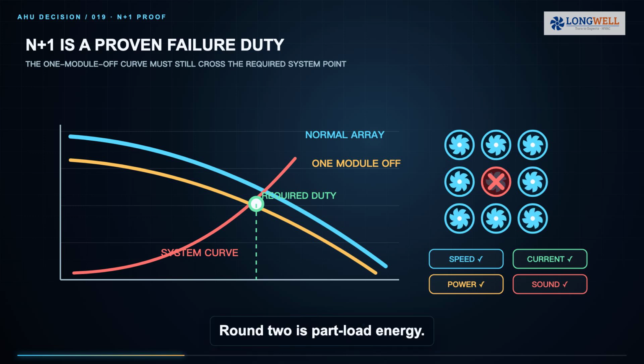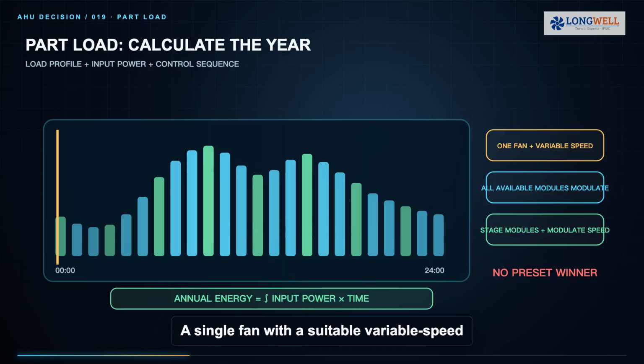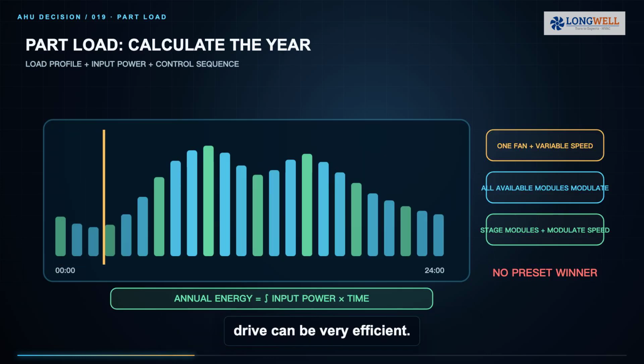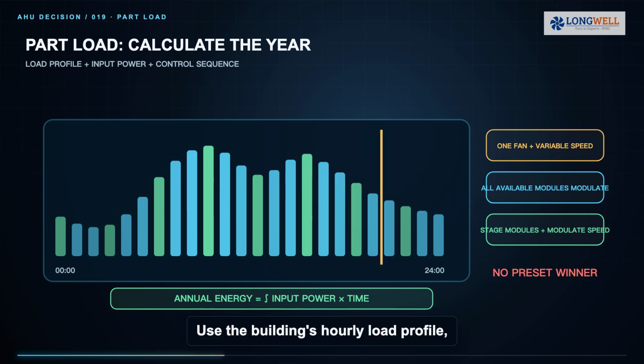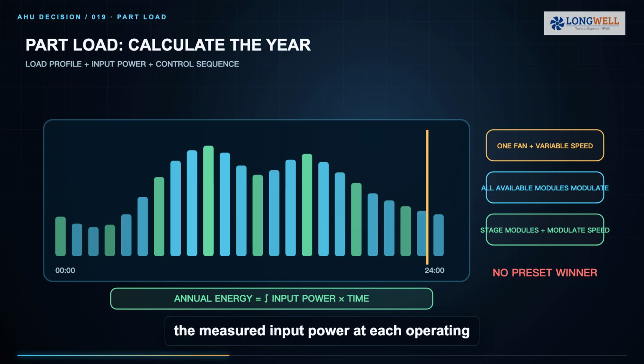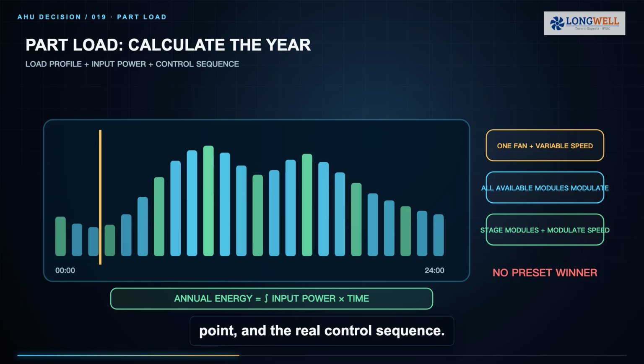Round 2 is part load energy. A single fan with a suitable variable speed drive can be very efficient. An EC fan array can run all available modules together, or stage modules and adjust the speed of those that remain active. Neither architecture automatically wins. Use the building's hourly load profile, the measured input power at each operating point, and the real control sequence. Annual energy is the area under that power versus time record, not a percentage printed beside a layout diagram.